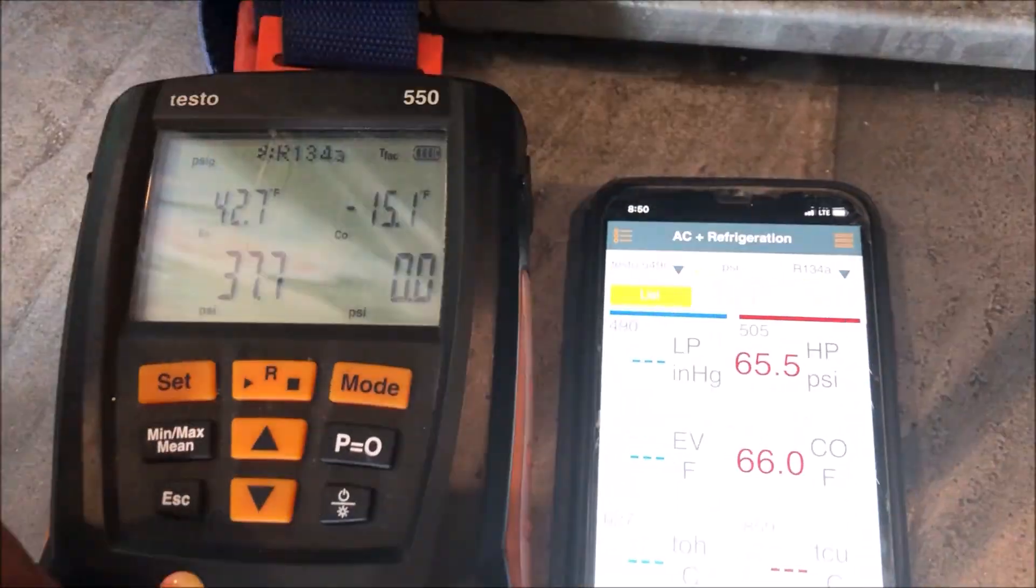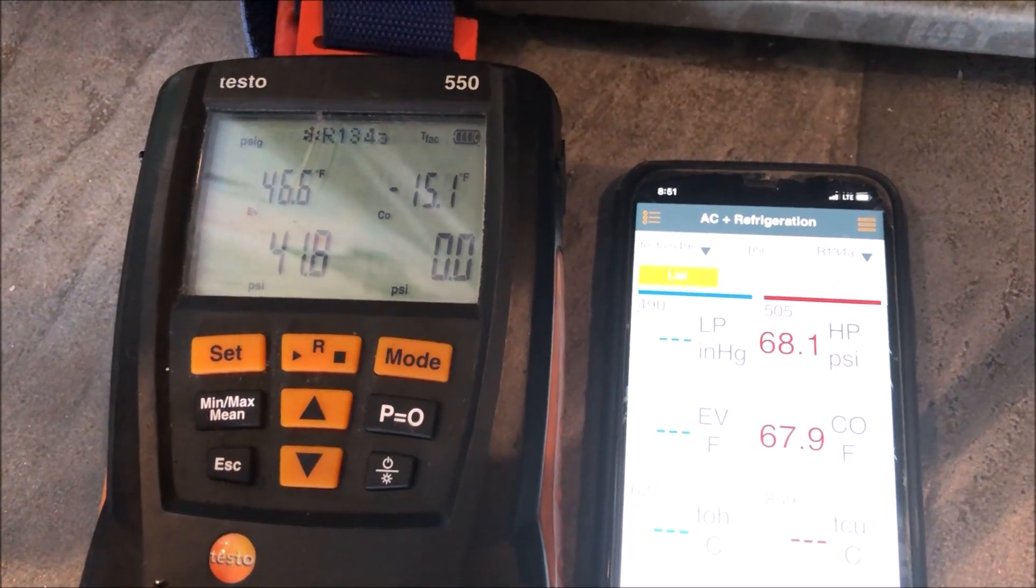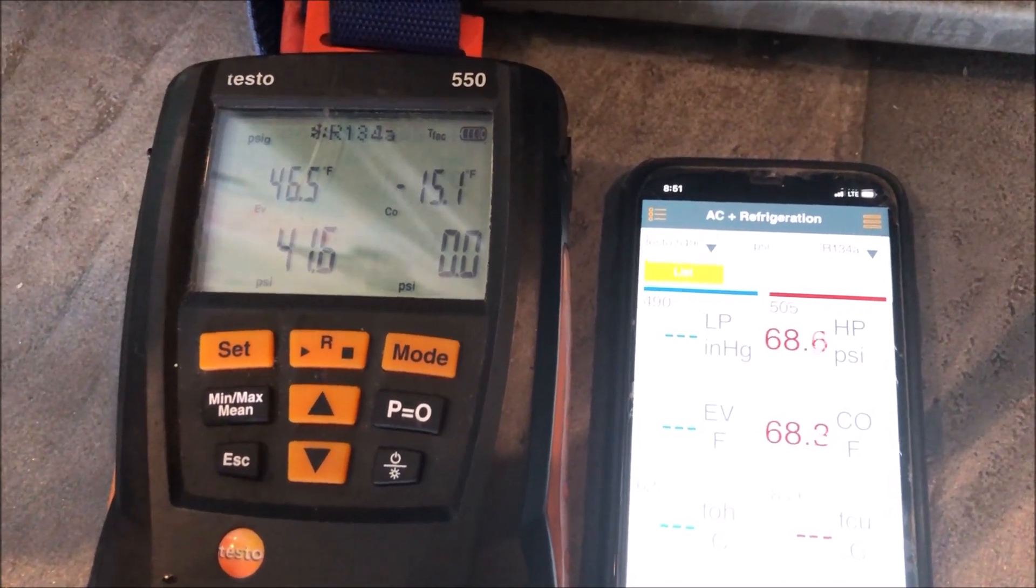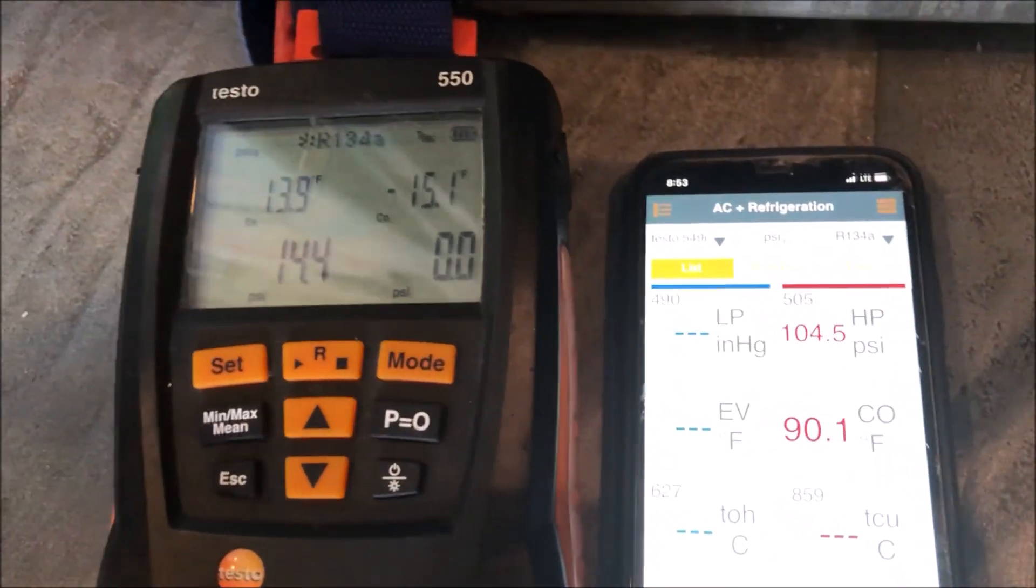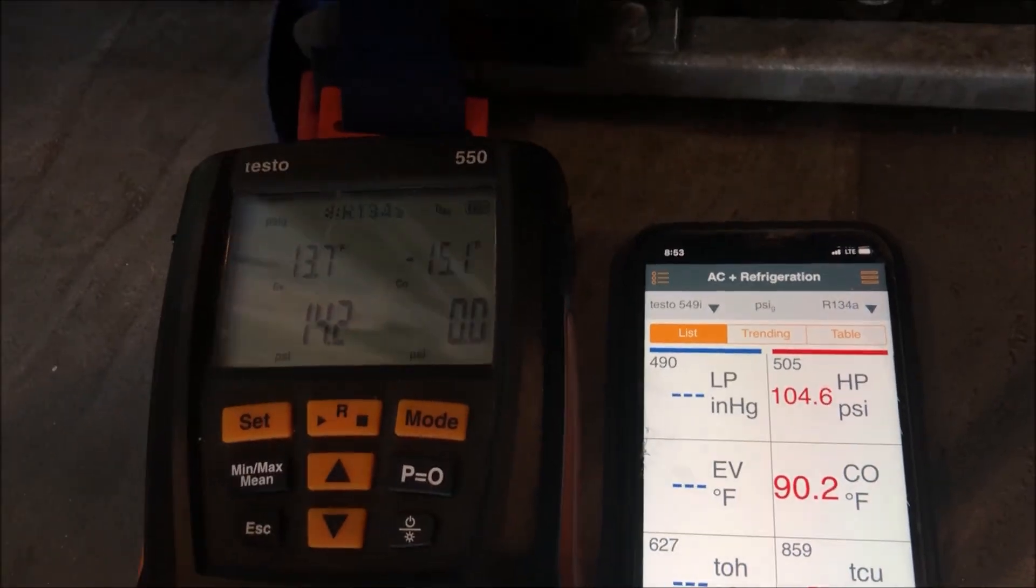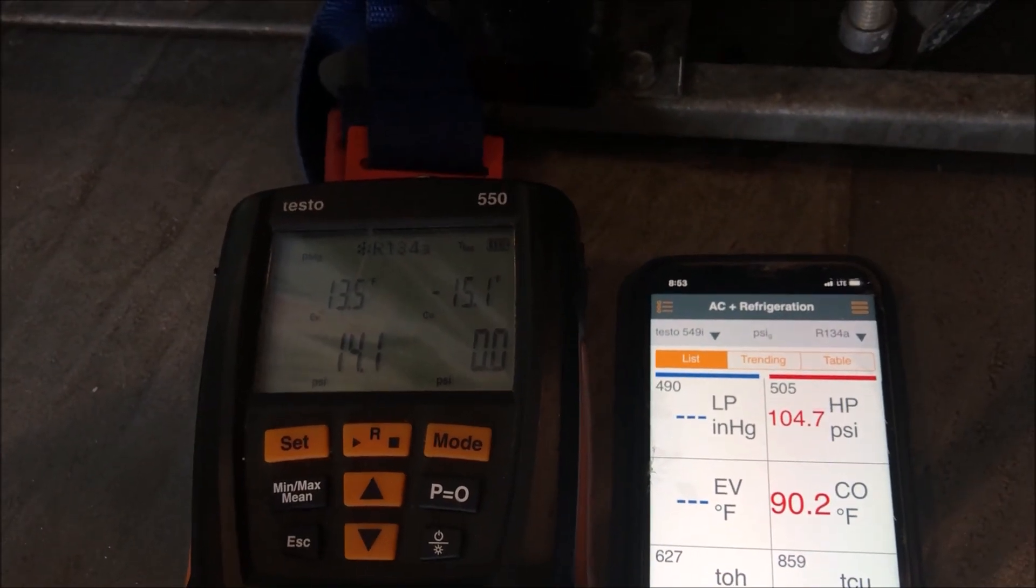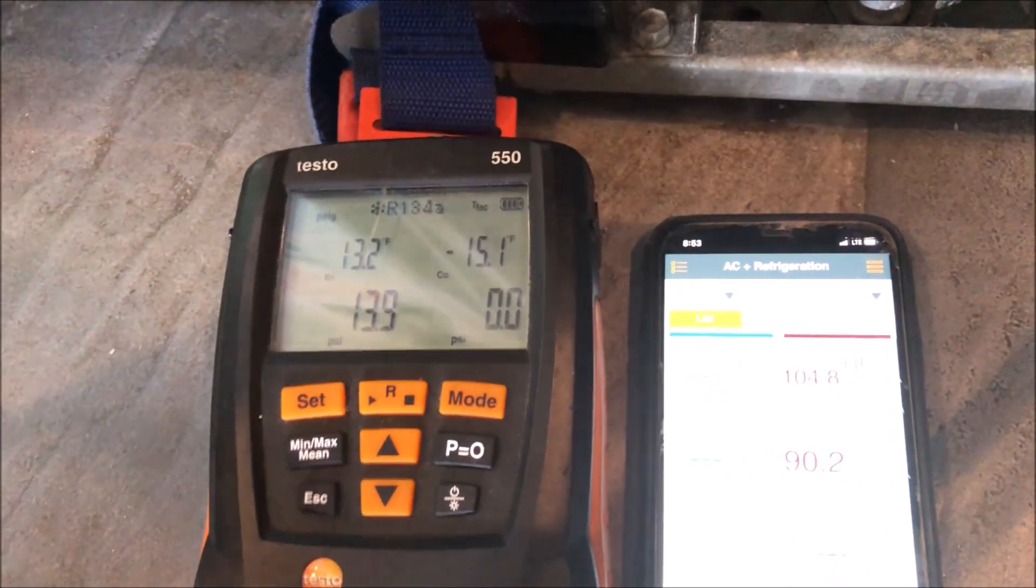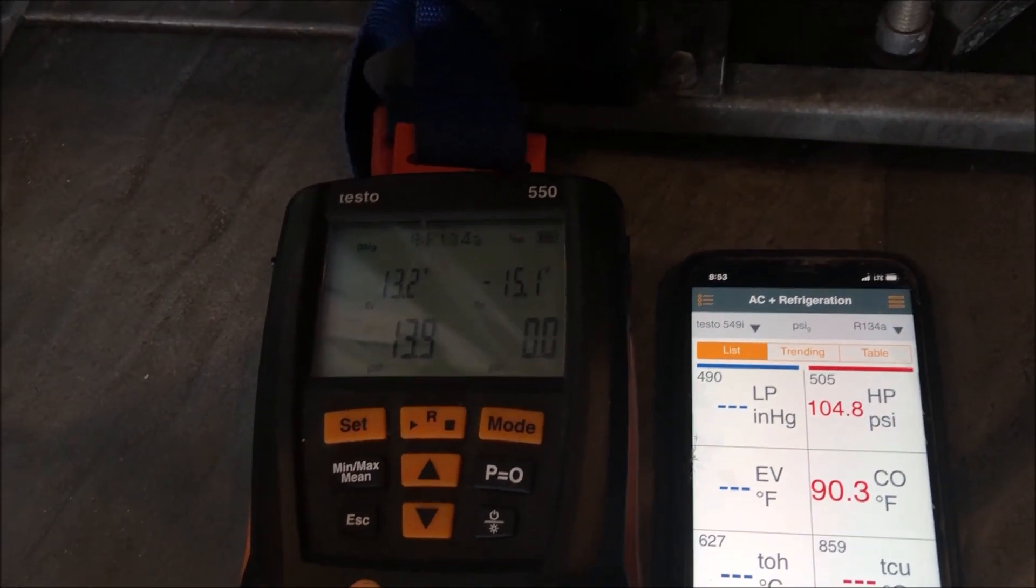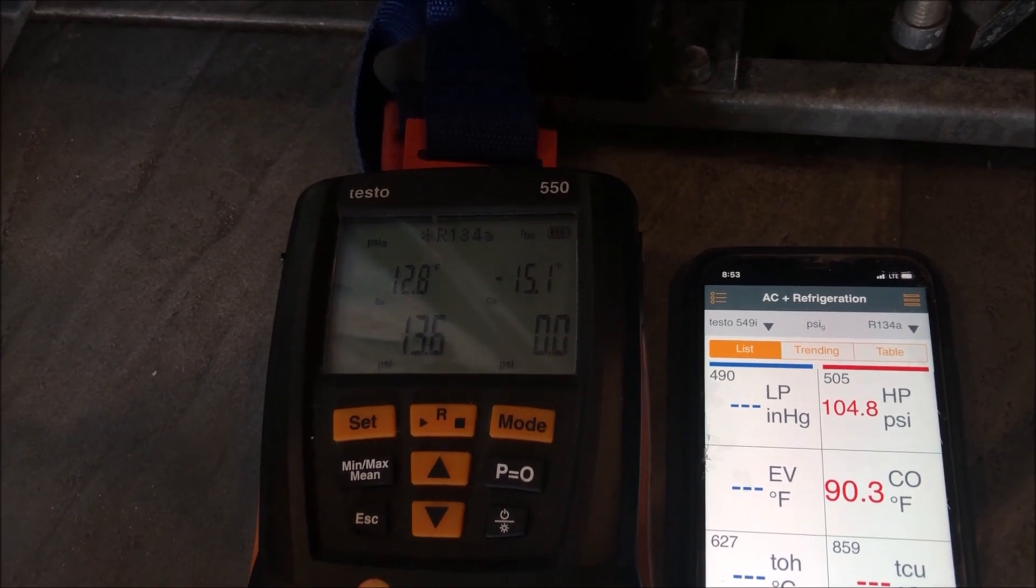I'll just quickly hit fast forward here. We'll get the full charge, 10 ounces in. All right, we got our full charge in, we're all good. Let's go ahead and close our valve off. And as you can see, we're down to 14 PSI, 104 head pressure, which is 90 condenser saturation. So that's giving us somewhere around an 18 condenser split, which is good. We're looking for a 15.